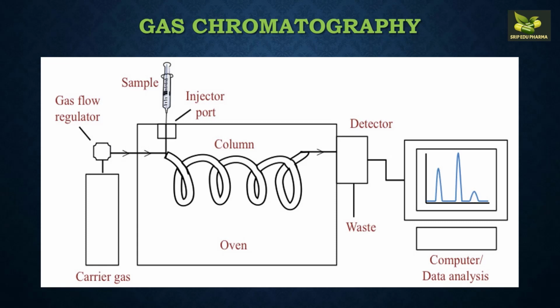But the liquid samples have to be dissolved in a particular solvent and then injected by micro syringe at the injector port. The principle remains the same. Within a fraction of a second it gets vaporized, and along with the mobile phase it is diverted towards the column. And if the sample is a gaseous one, then one has to use an extra system near the injector port, that is nothing but a gas valve. Through this gas valve, the sample gas is passed into the oven.